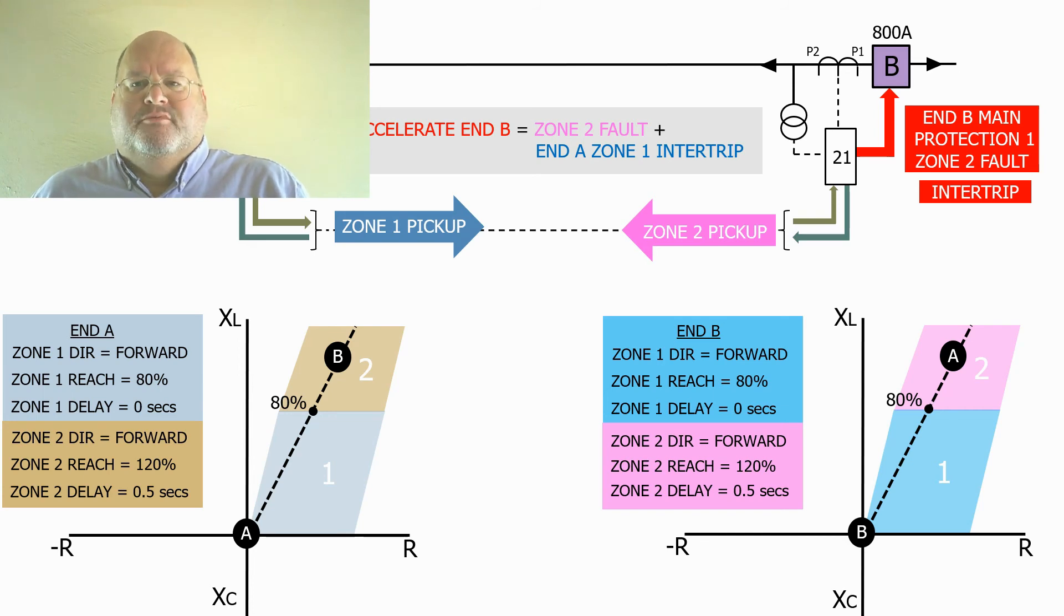What happens if we lose the communication system? Well, the scheme will then revert to its original mode, which is a delayed tripping on zone 2, i.e. a simple distance scheme.